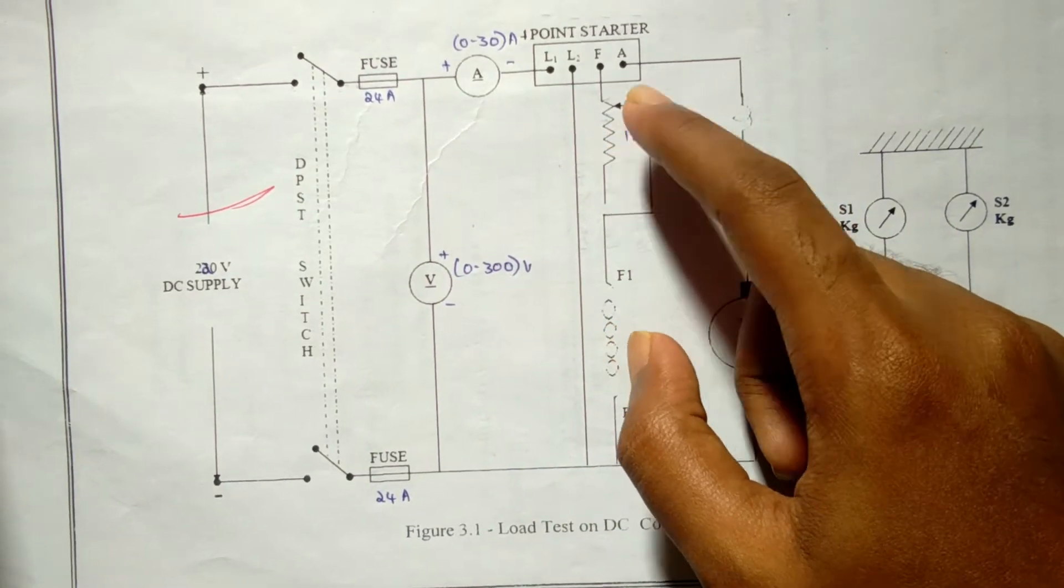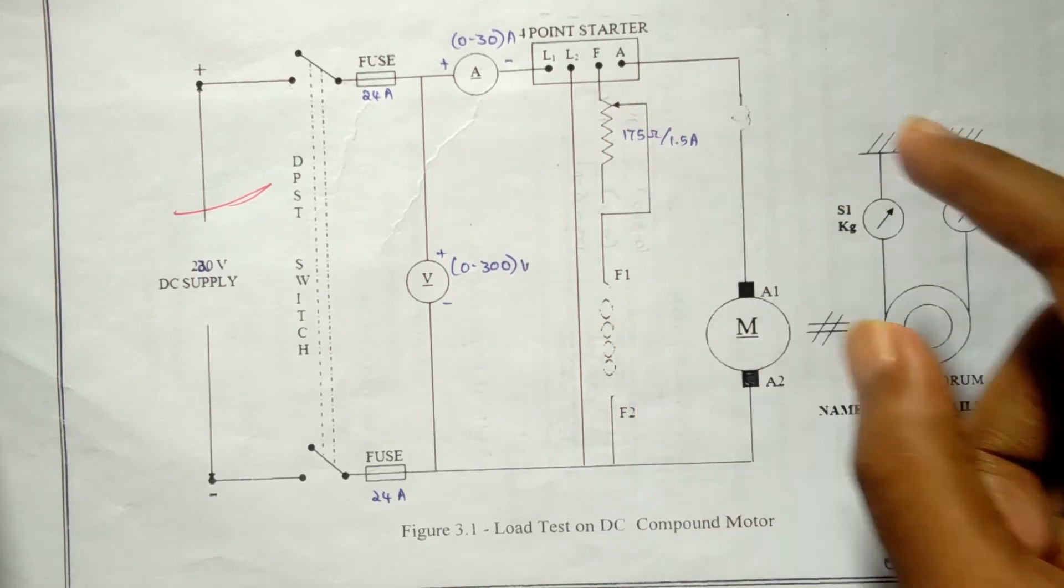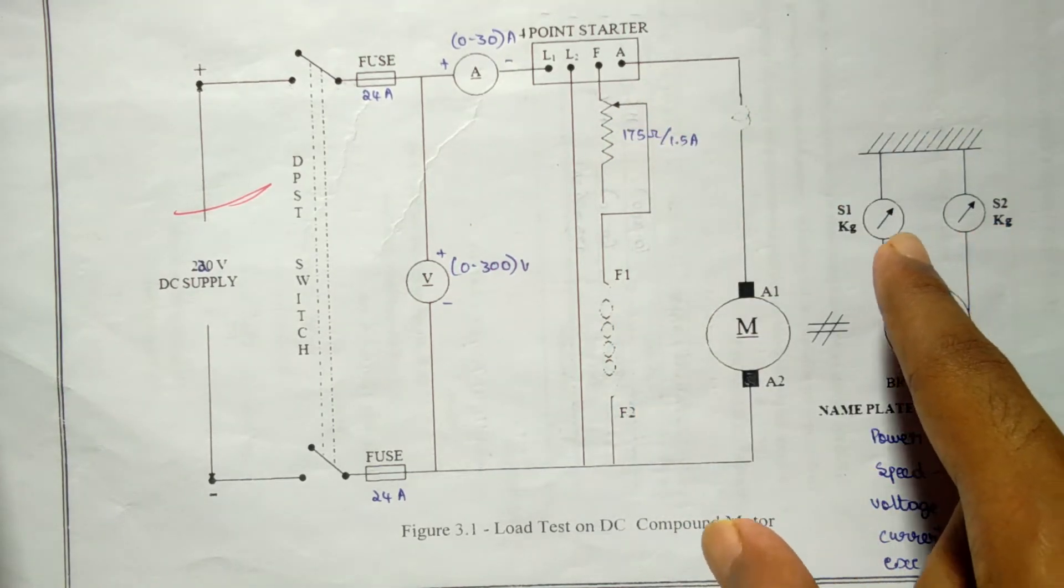The motor field rheostat should be kept at minimum resistance position at the time of starting. Heat produced due to the friction between belt and brake drum is reduced by pouring water inside the brake drum periodically.